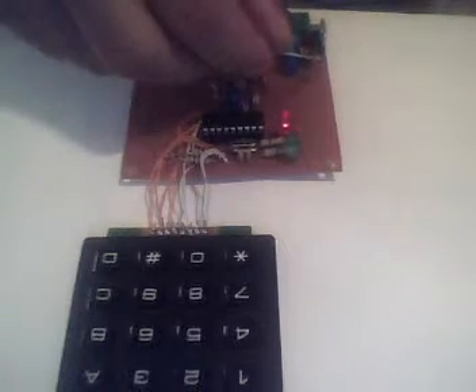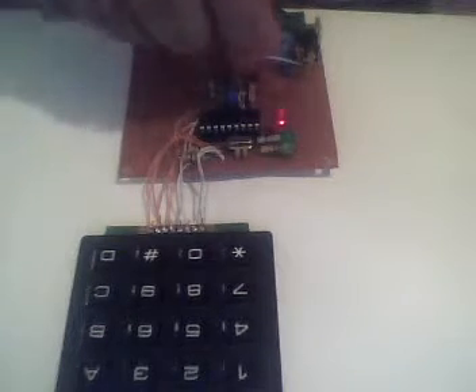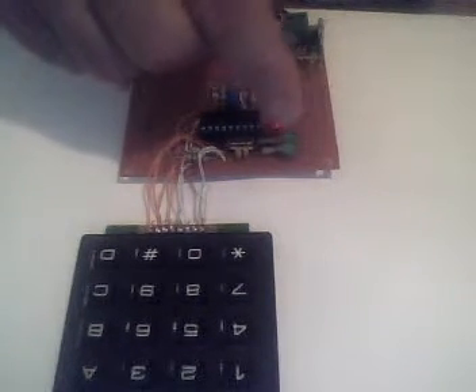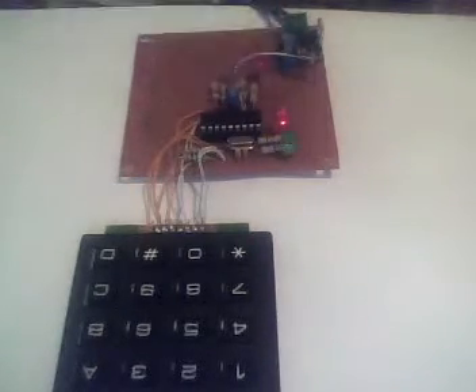This is a limit switch for the door. That means the door is closed. This one, the green LED, means that the door is open. This red LED means that the lock is open. Let's check together.